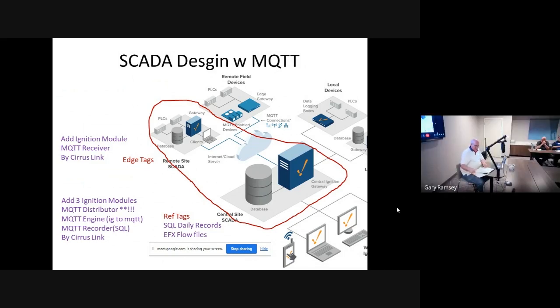Okay, back to the design. This is the design when you plug MQTT back into the SCADA system. You still have the edge gateway, and you put an MQTT module on it to send and receive. On the main gateway, you put on a distributor, you just need one of those to have an MQTT network. You put on something called the MQTT engine, which translates from MQTT to Ignition, and that's where the tags live on the main gateway. Then there's this handy thing called MQTT recorder, which takes those daily records and puts them in SQL for data reporting.